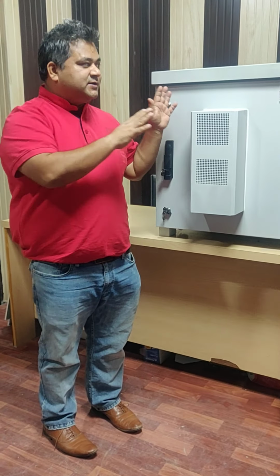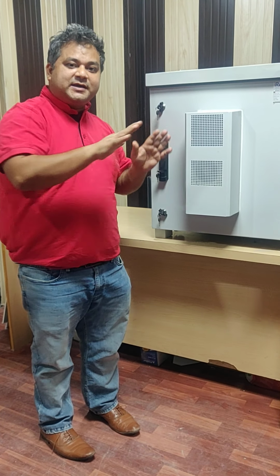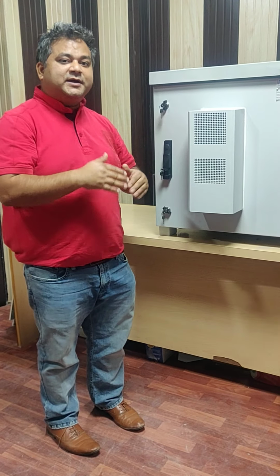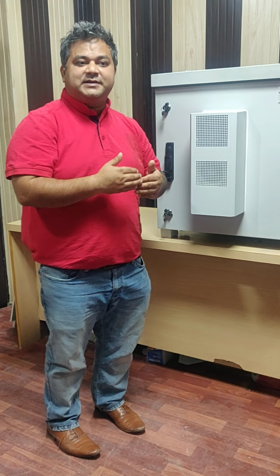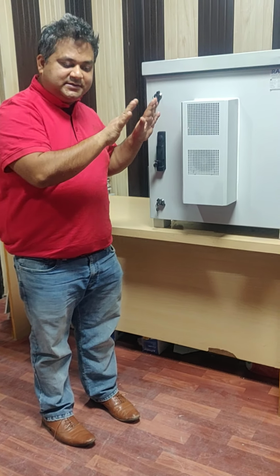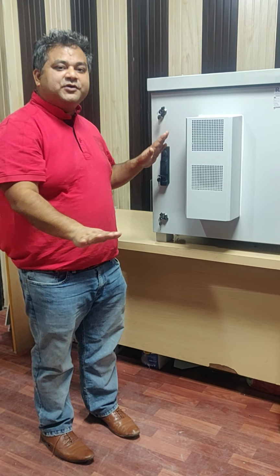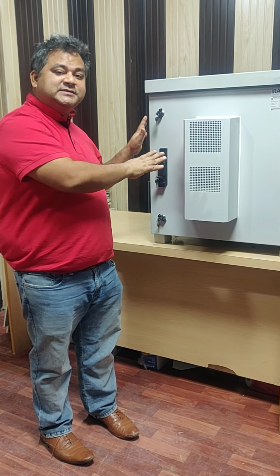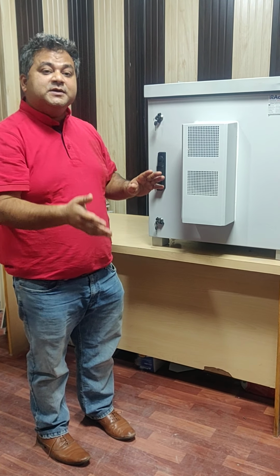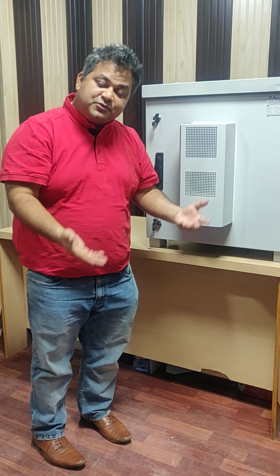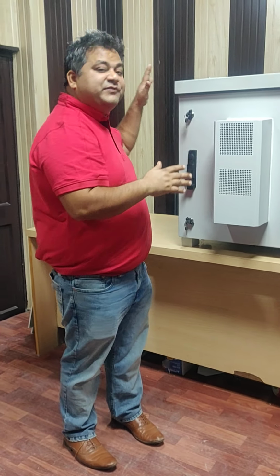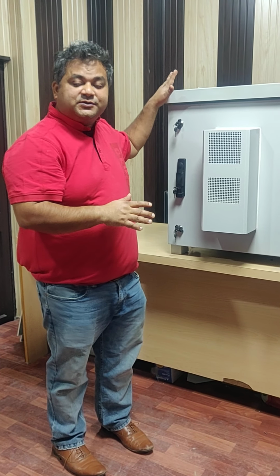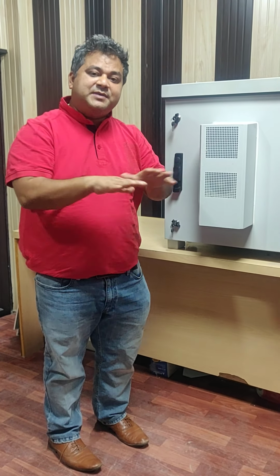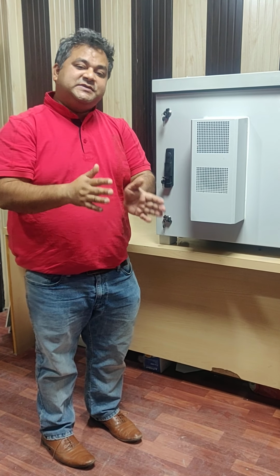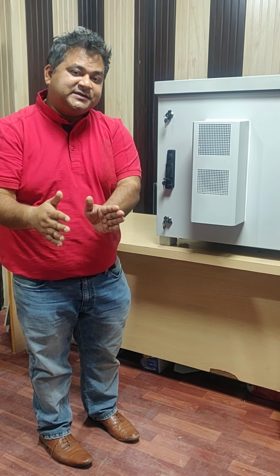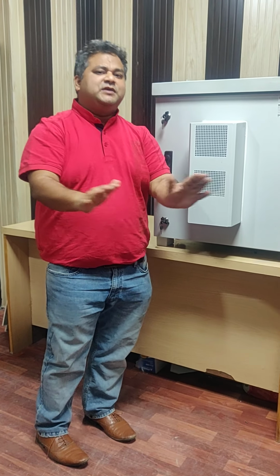This helps when your rack is placed in full sun exposure, so it can maintain a certain temperature. If the outside temperature is 40 degrees, in sun exposure the inside of a normal cabinet can reach 45 degrees. Using an outdoor double wall cabinet prevents sun exposure heat from entering, so it maintains roughly the same temperature as outside - around 40 or 41 degrees.